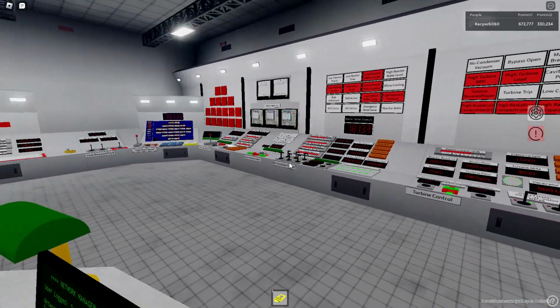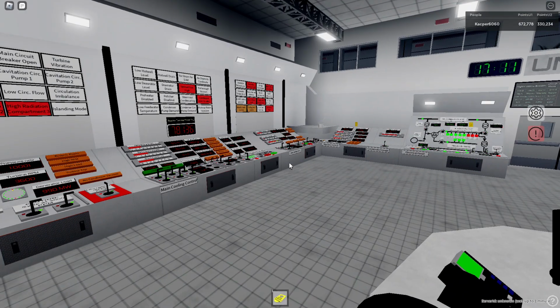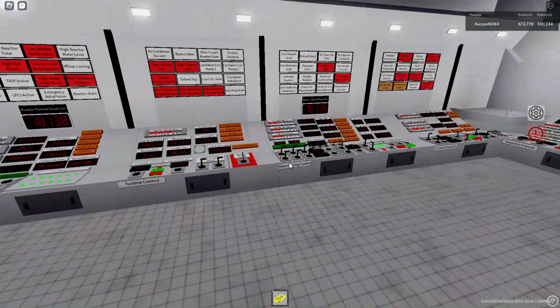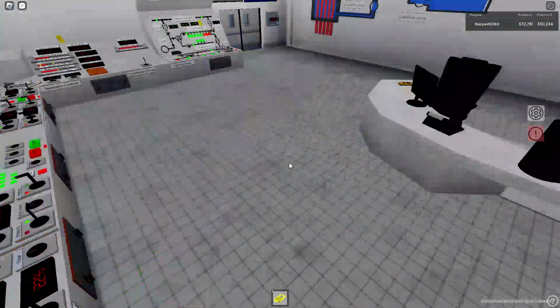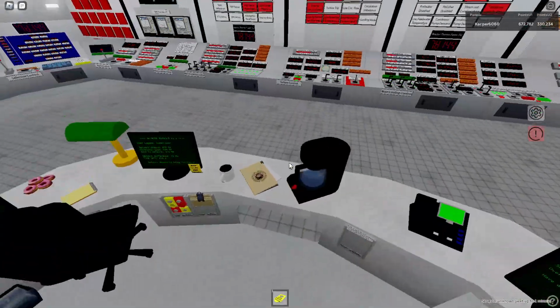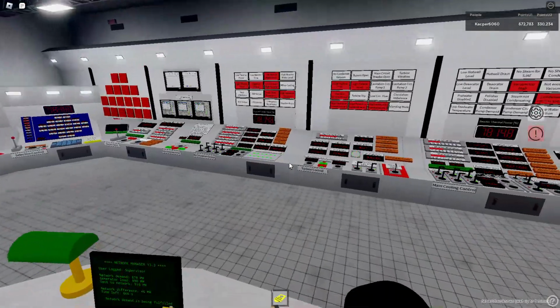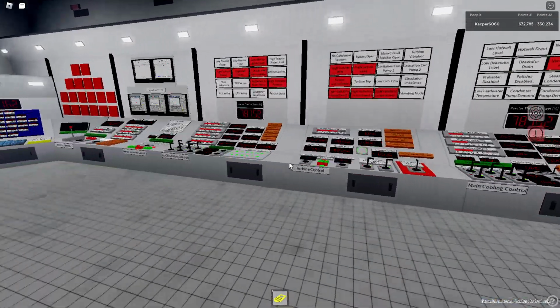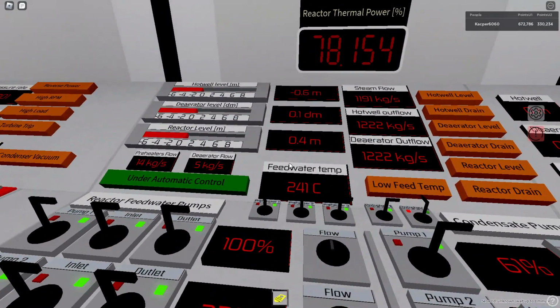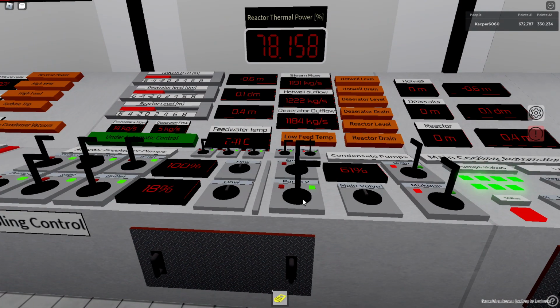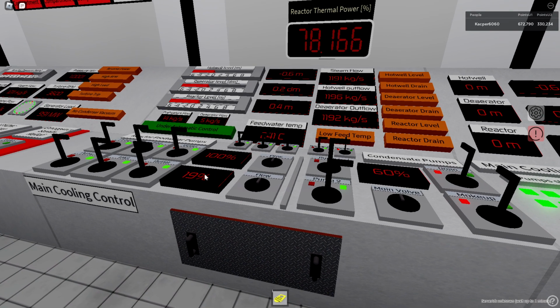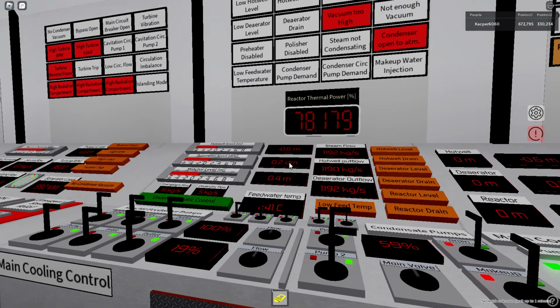Having one of these on means 1 less point a second. When full manual, you get 1 point a second here. In Unit 2, including turbine full manual, you get 4 points every 3 seconds, or 1.33 recurring points a second. So as with demand, you'd want to readjust the flows. What 1% here basically means is 10 kilograms per second, around that. Now the flows are matched.